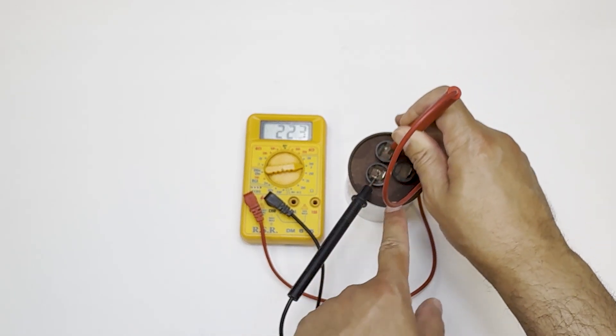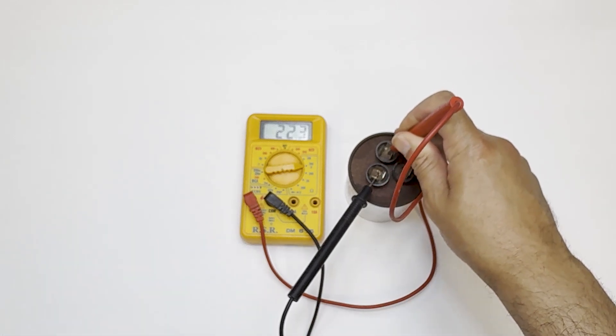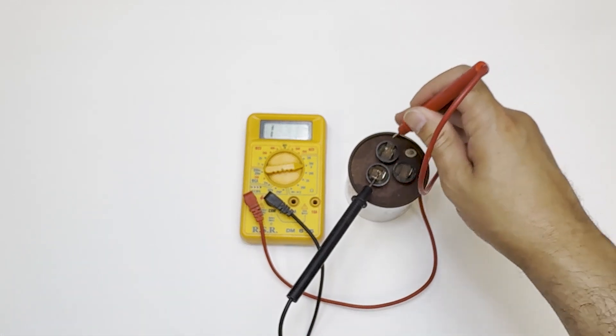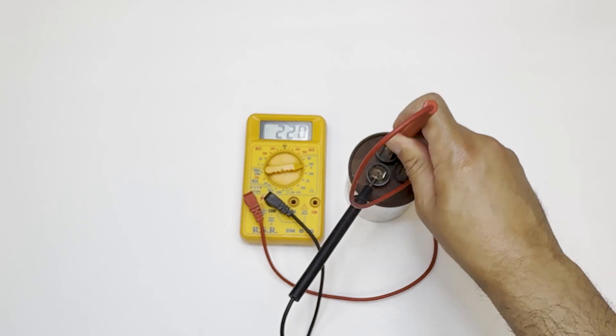Now let's try the HERM side. You'll see the meter jumps and climbs, then eventually drops back. So the compressor side still kind of works, but since one side is shot, the whole capacitor is basically useless.